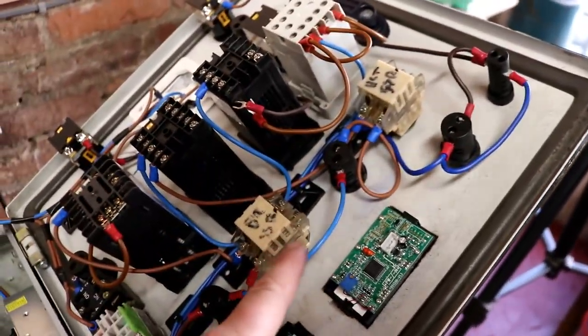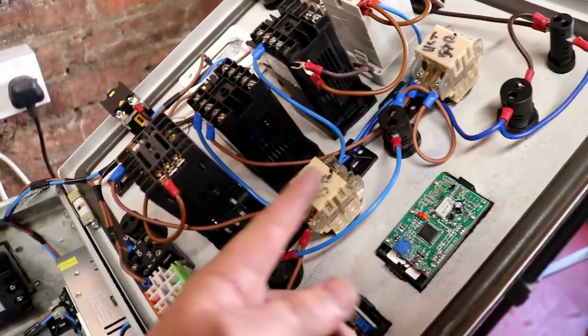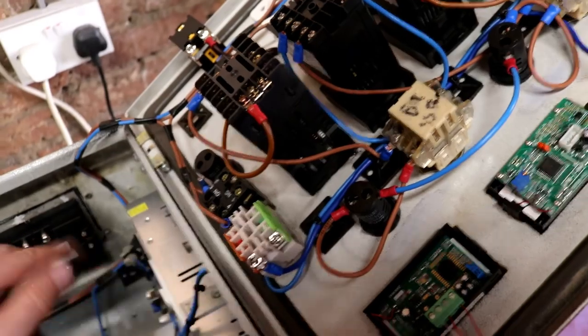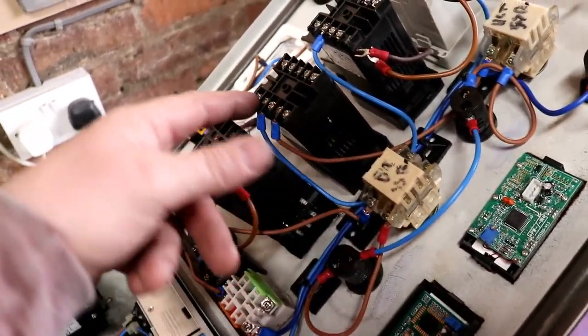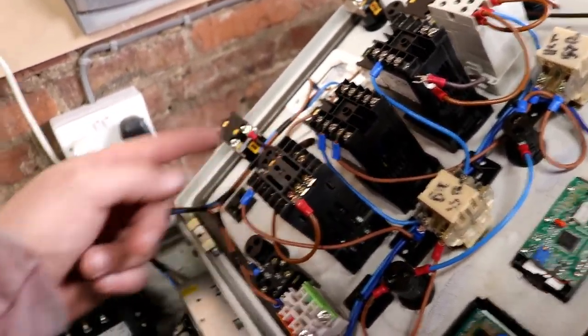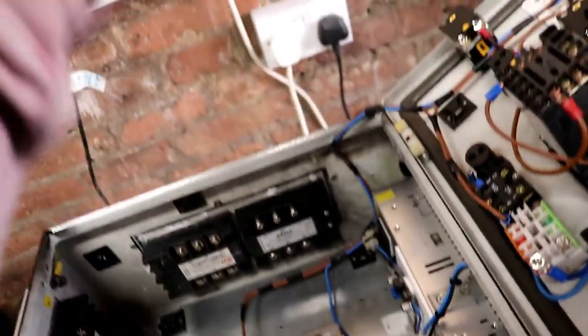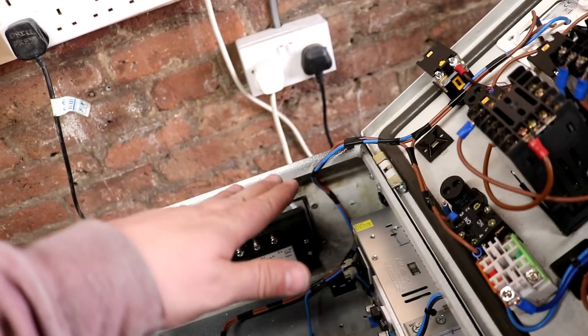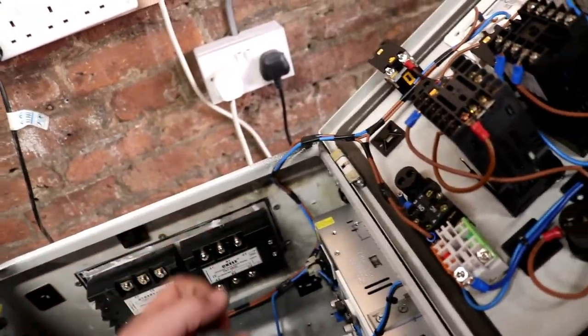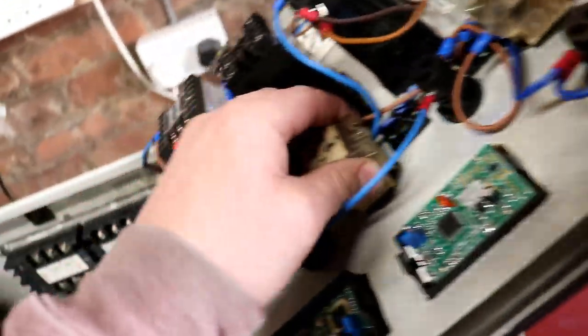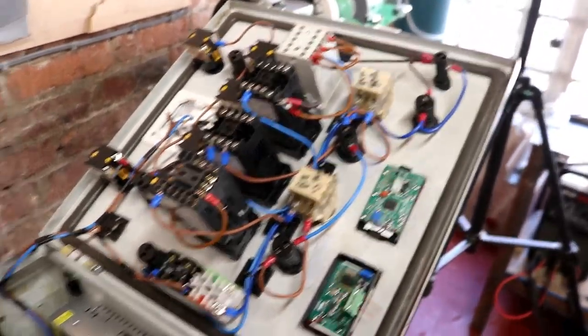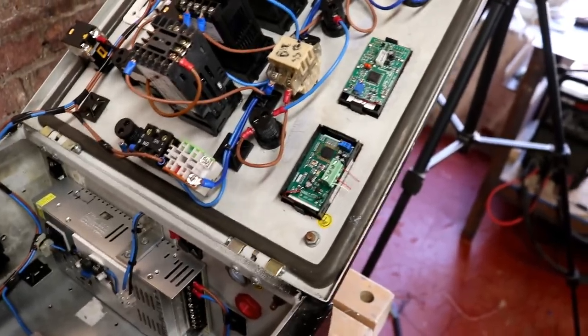A little bit more in now. We've figured out that these two switches here are going to switch the relay side 12 volt supply. If we turn that off we isolate the solid state relay, no power to elements. Before we feed the power into here, this also has to go via a relay and that relay will be powered by a float switch, a level float switch in the tank. When the tank's full of water it energizes, closes the contacts which will allow current to flow through here and we'll control it with these red switches.